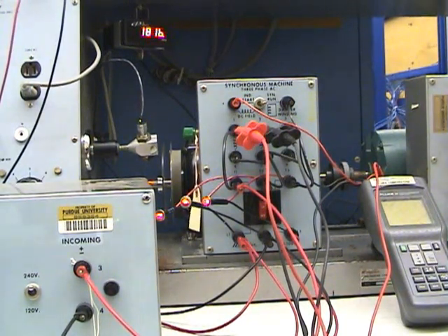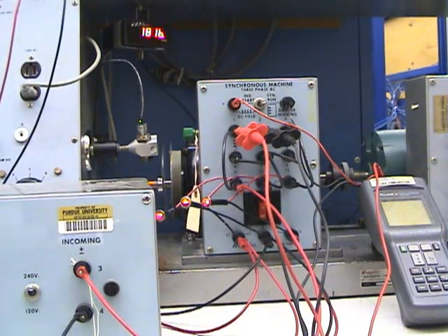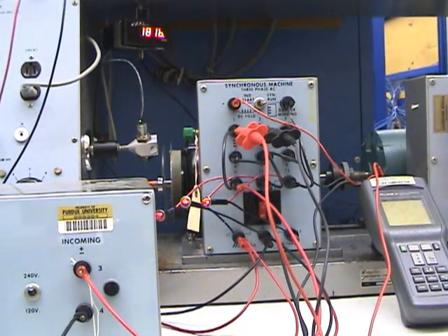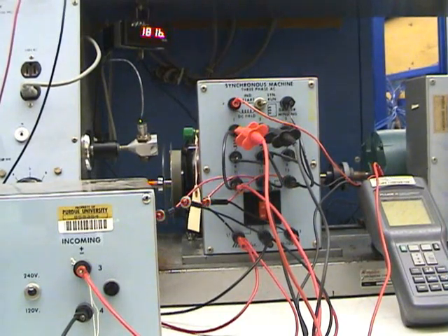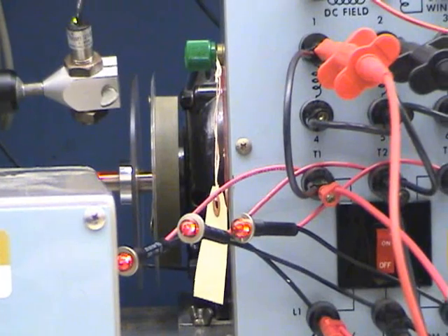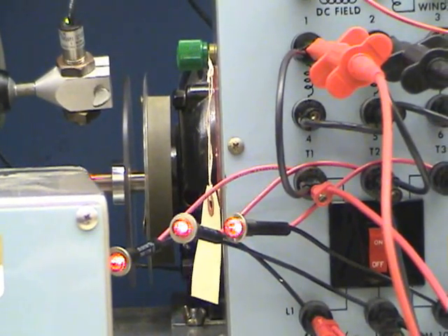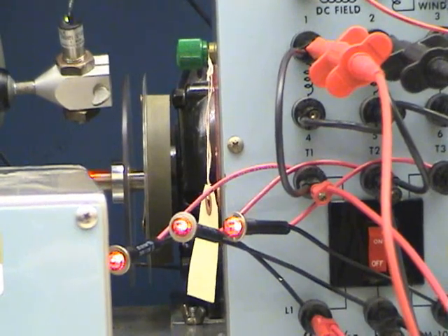Now I've got the generator running just slightly above 1800 RPM, which of course is at synchronous speed. And notice here that the lights are flashing on and off. I'll zoom in on those. You see the lights are flashing on and off. They're all in synchronism, so that means that we've wired the phasing correctly.